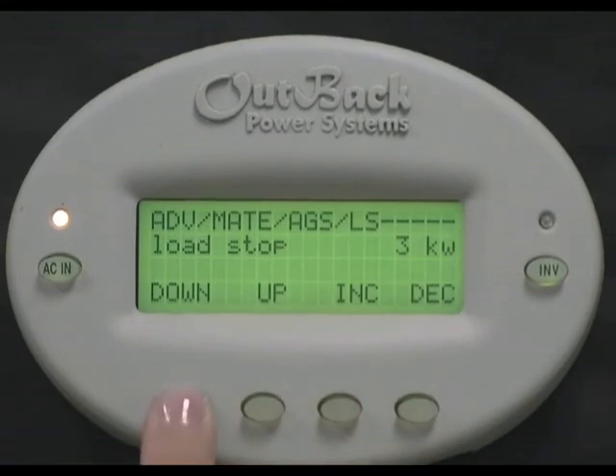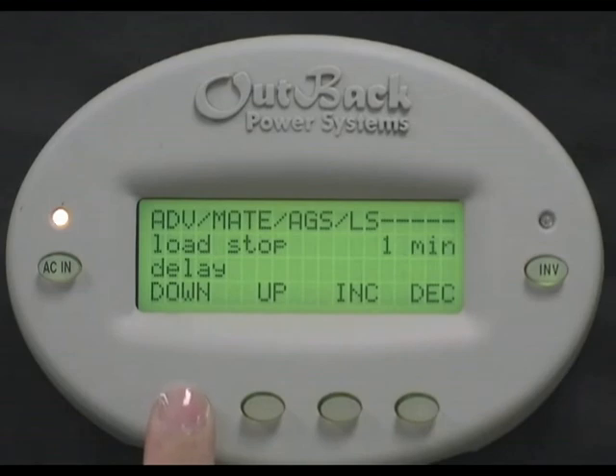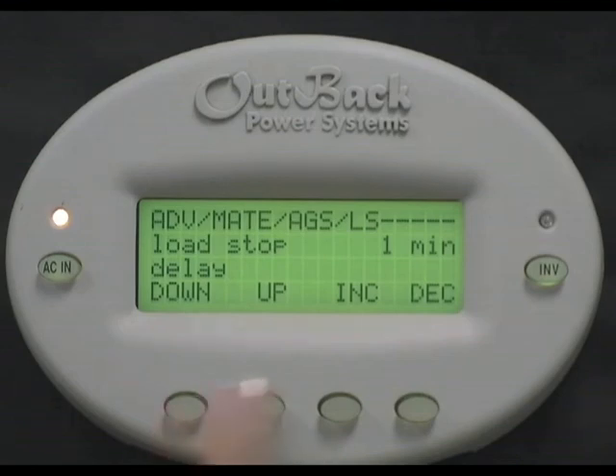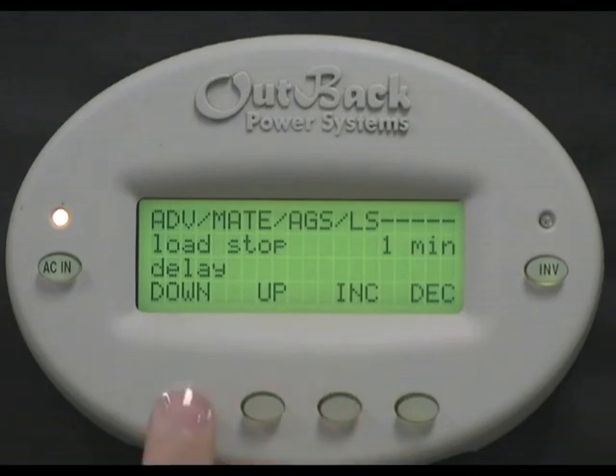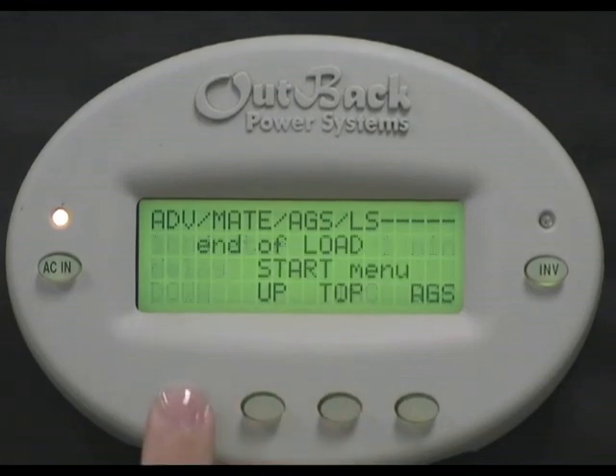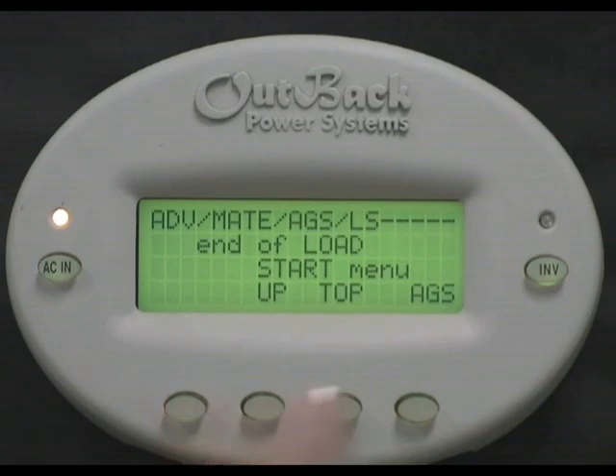Load stop delay is how long the load demand must be under that 3kw set point before the inverter will tell the generator to turn off. Press increase to change the set point. For our example, we will leave it at one minute. End of load start menu. Press AGS.